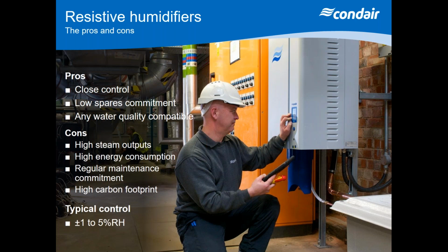With these, also, you can run them on different types of water. So you can run them on your raw mains if you want to. You can run them on softened. Also, you can run them on RO water as well. So they're very compatible with different types of water. Ideally, we would normally recommend RO water, because you're taking 90% of the solids out, and that allows you then to reduce the number of maintenances you're having involved with the equipment. And also, if you're draining less with the system, you're reducing the amount of wasted energy to drain as well. So that's an added benefit of RO, albeit your water consumption may go up. So that's another thing you've got to consider.